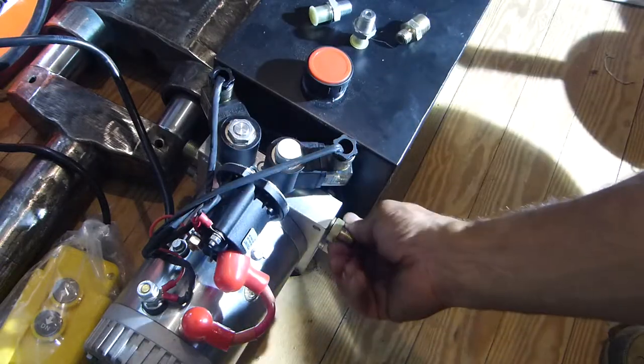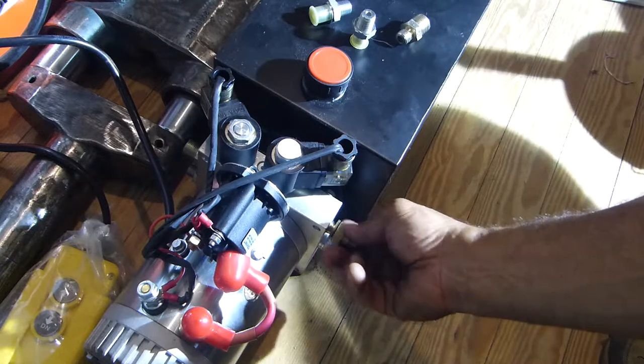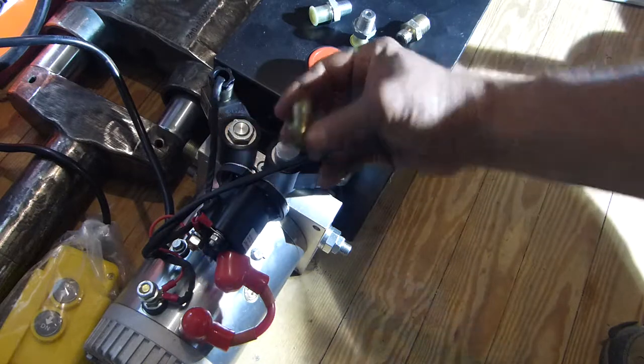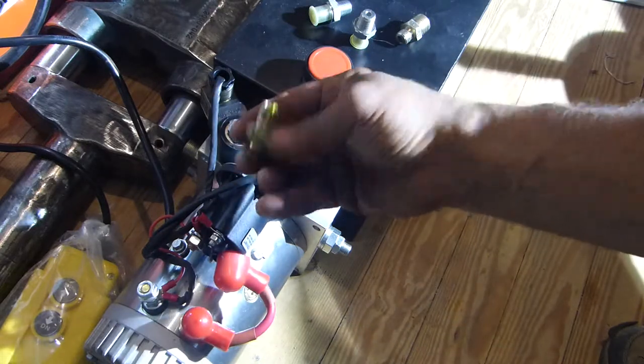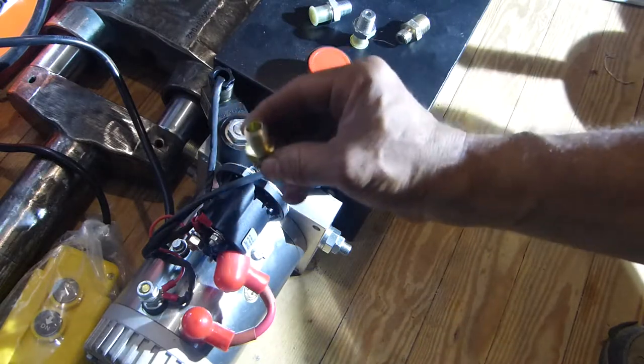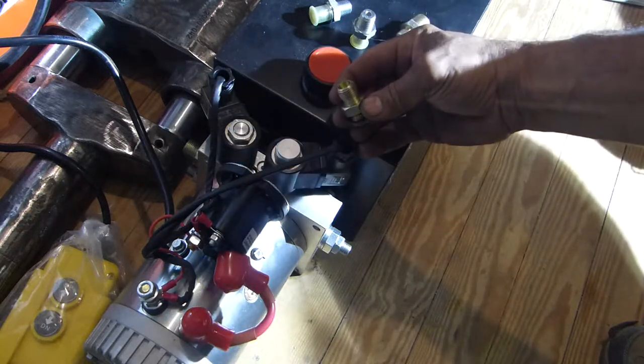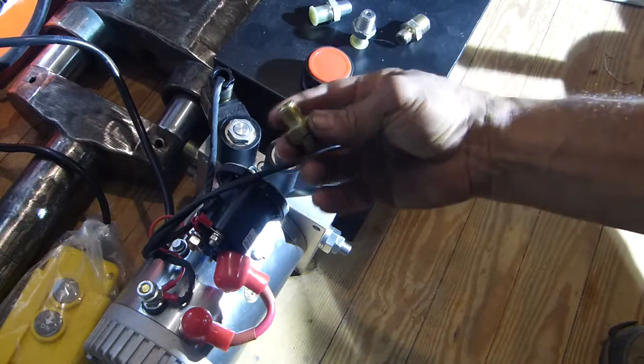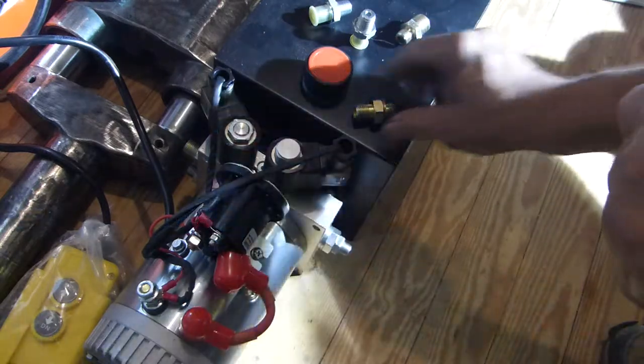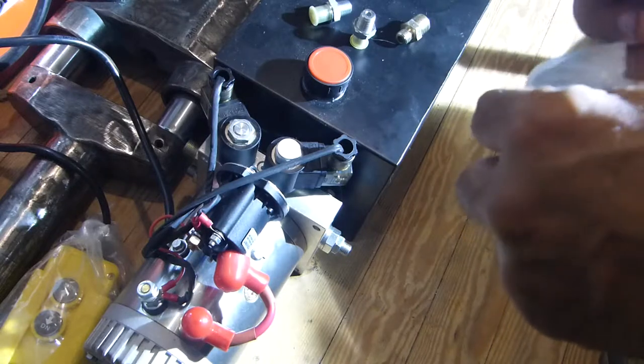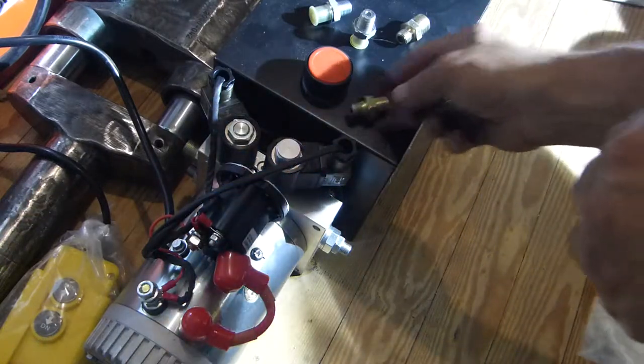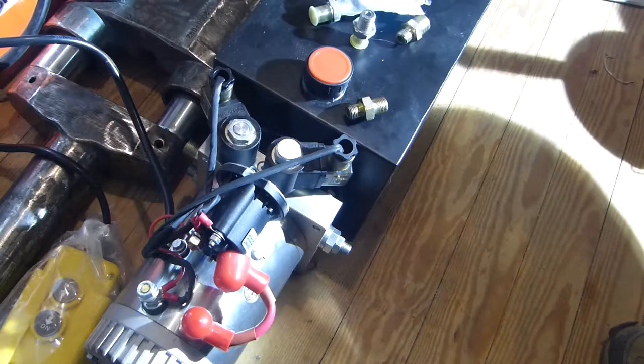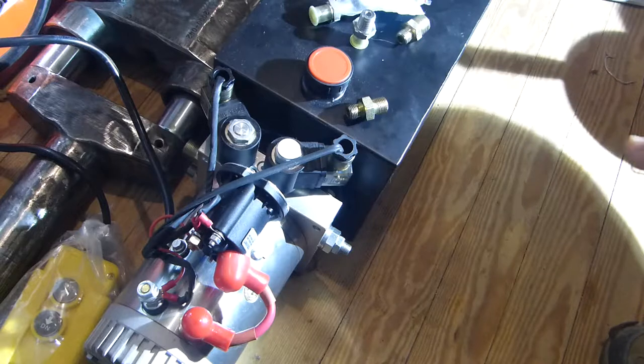The toughest part was finding out how to do this transition. What do I think of the manufacturer's new replacement fitting? Looking at it and taking the measurements from it, this comes out to about 2800 psi. This is a 3000 psi pump. That is not a good thing. So I don't like the replacement fitting because of the way it roughly comes out in math with the dimensions of that fitting.